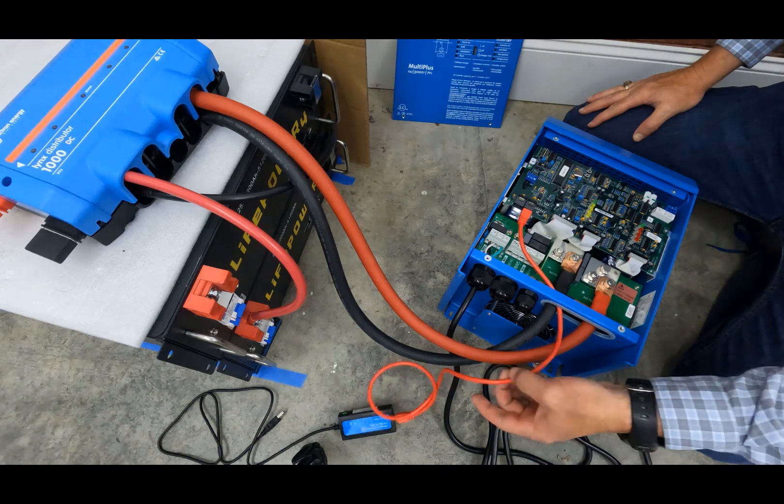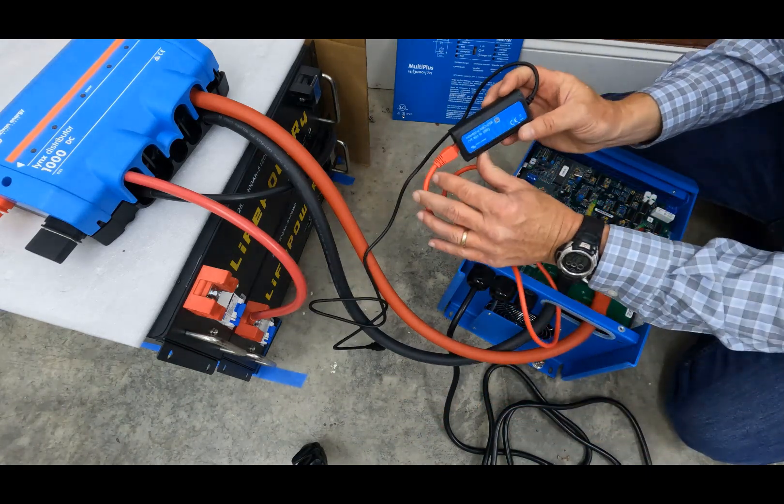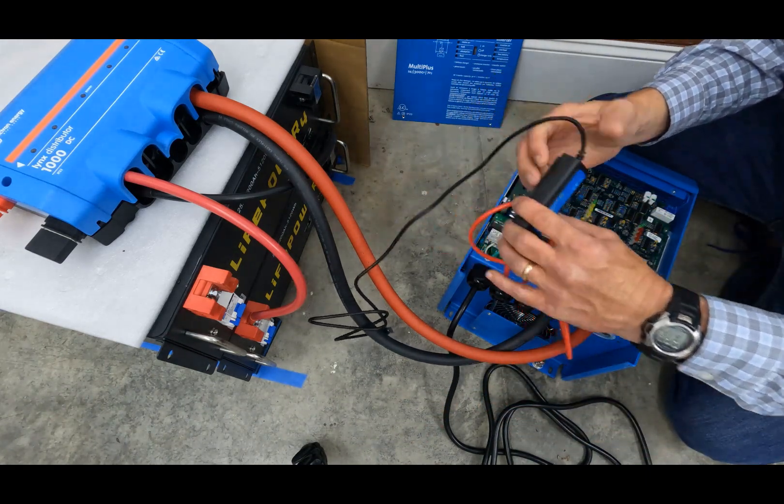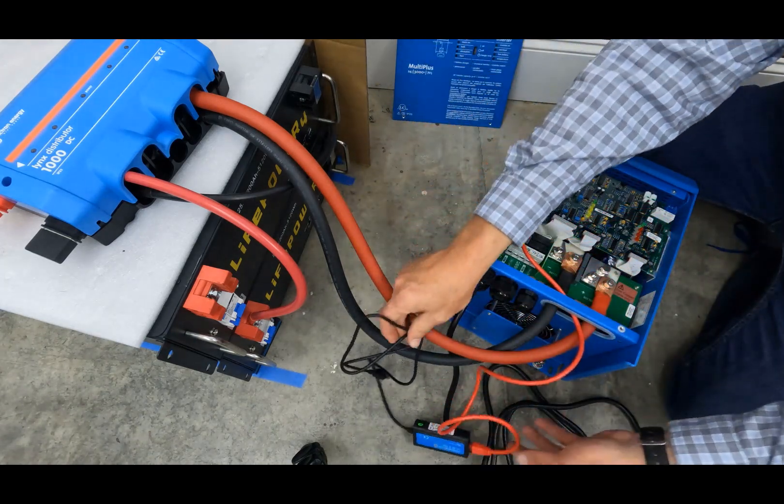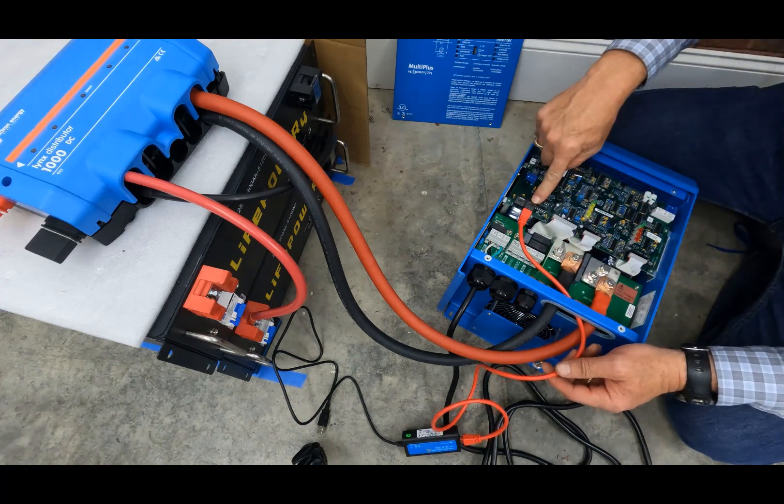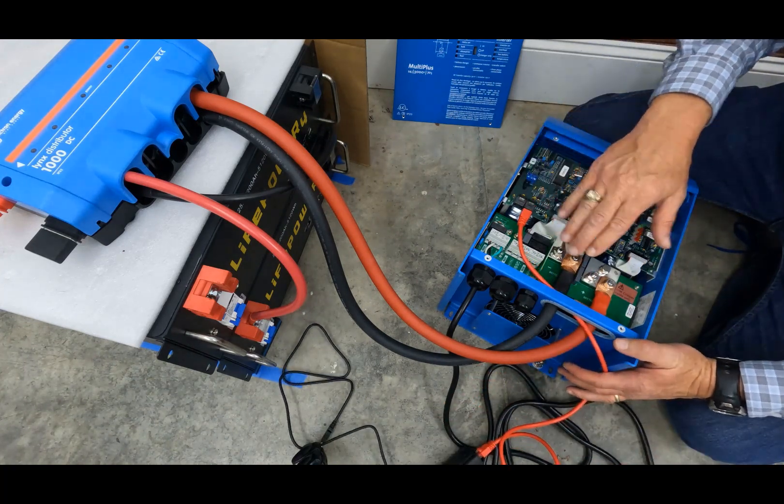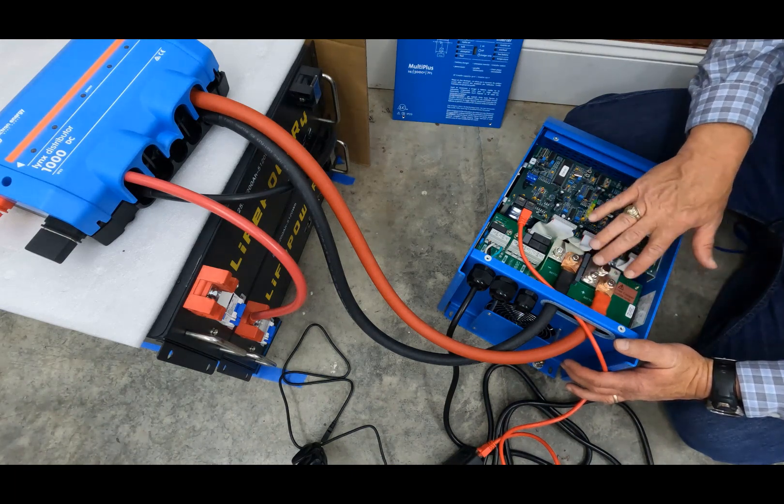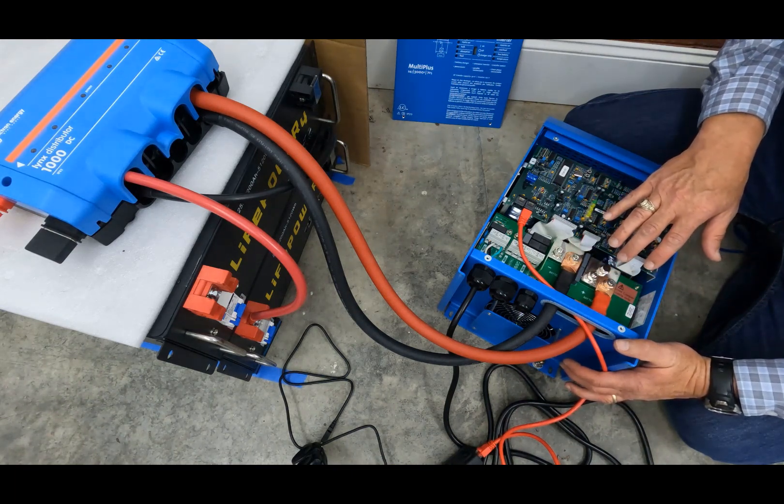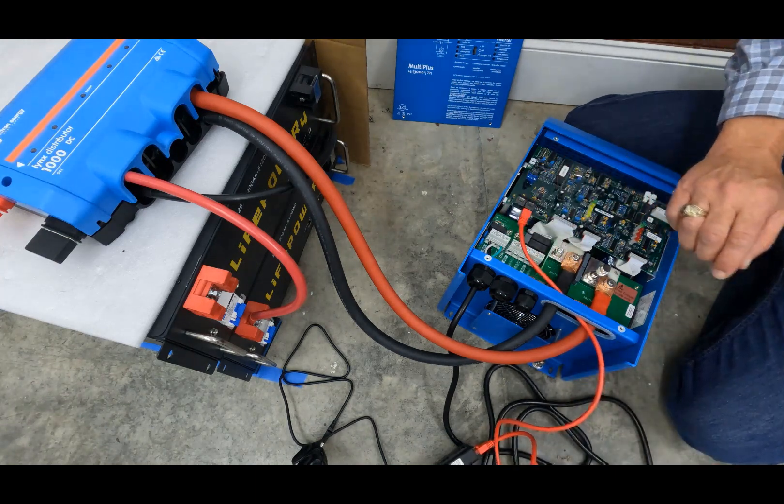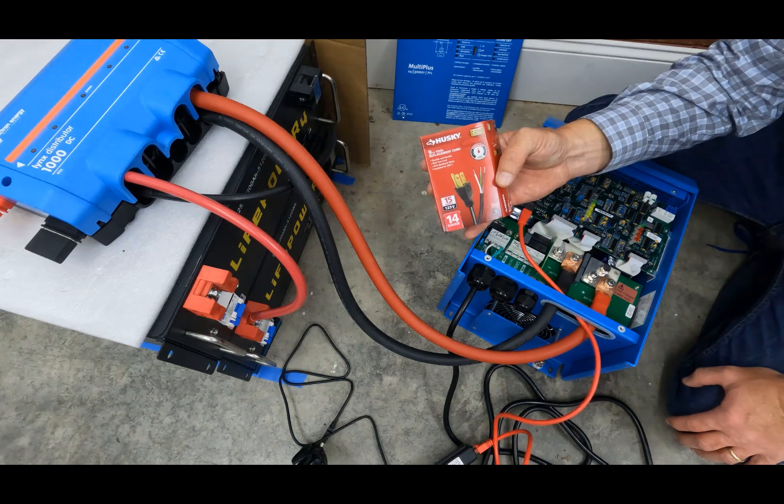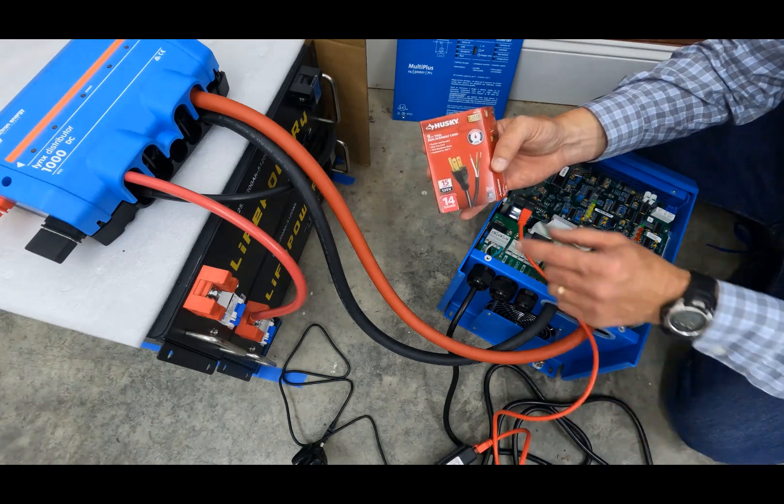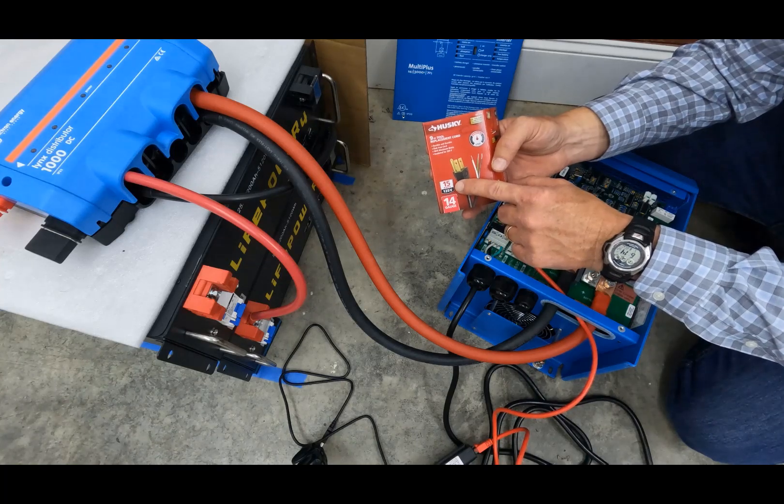Next, we've come back in, and you'll see that I have tied in the interface for the MK3. This will allow me to connect my laptop back into the inverter. I've just had this wired initially into one of the ports inside. The batteries connect primarily on the positive and the negative side here on the Victron on your inverter. And then I've gone in and I've used this little Husky nine-foot power replacement cord that I picked up at Home Depot. It is 14-gauge. It will handle up to 15 amps.